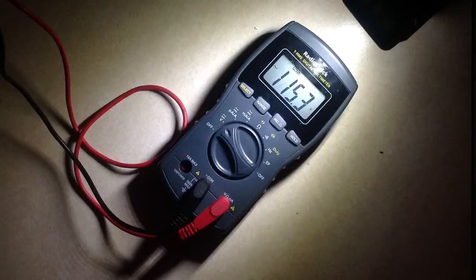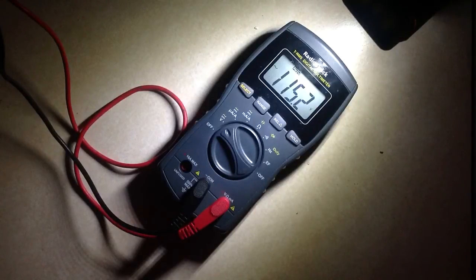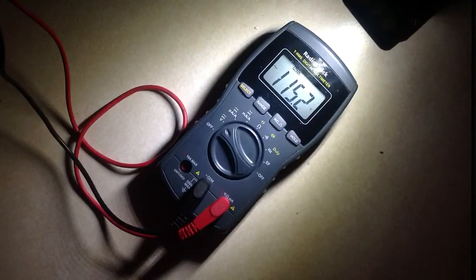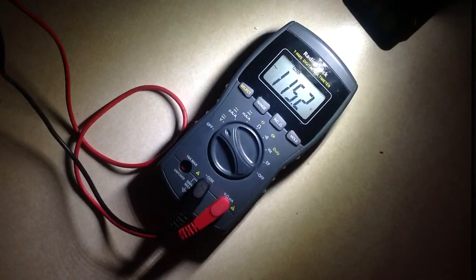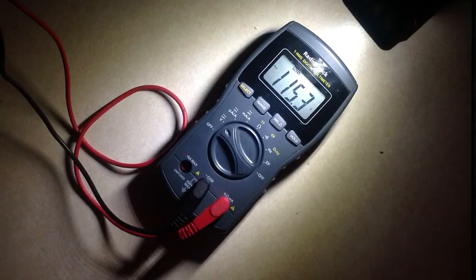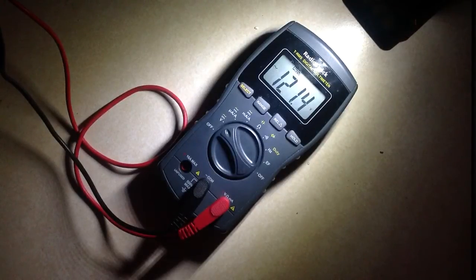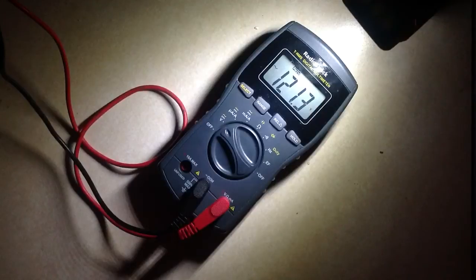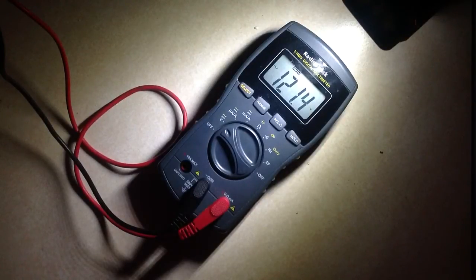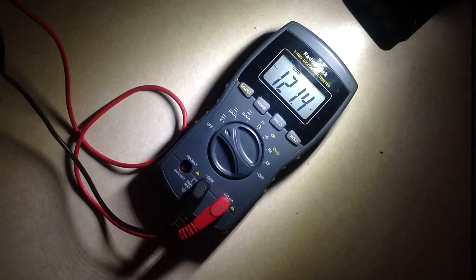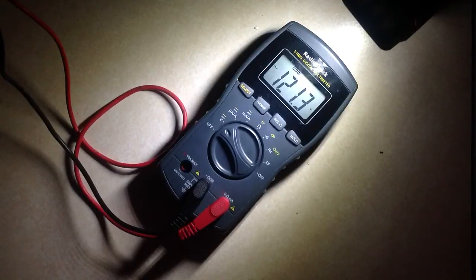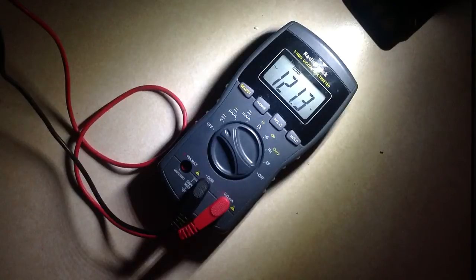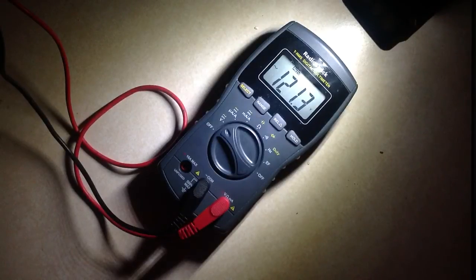Now, if it had dropped down to 90 volts, I would be really spooked because I would think that there was a bad connection somewhere in that circuit. And that could present a fire hazard. As for it dropping 6 volts like that, I don't really know exactly how serious of a problem that is. It's almost loading the circuit down all the way.